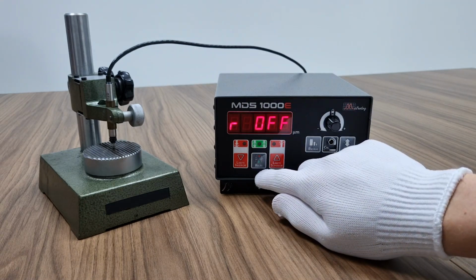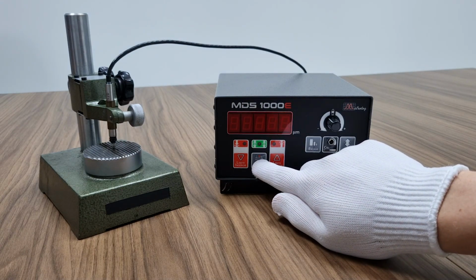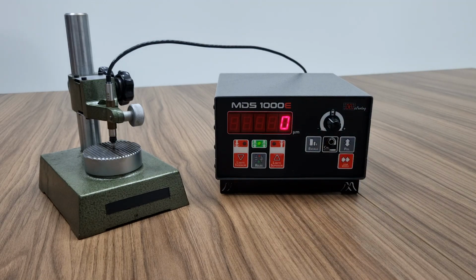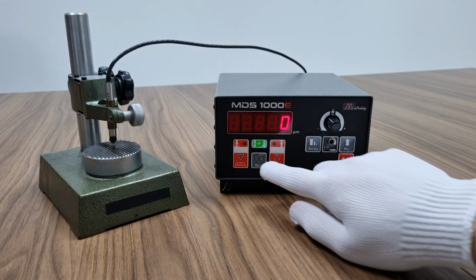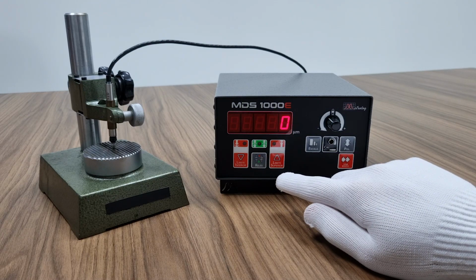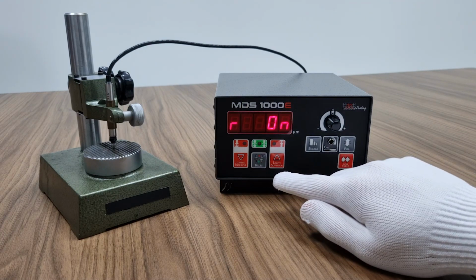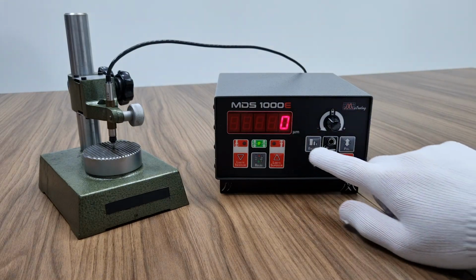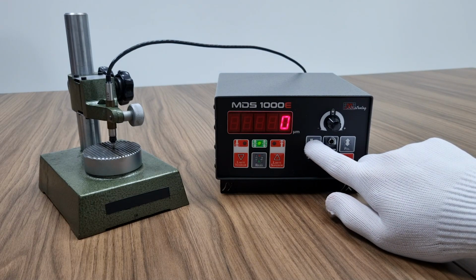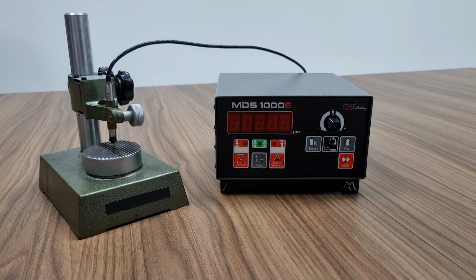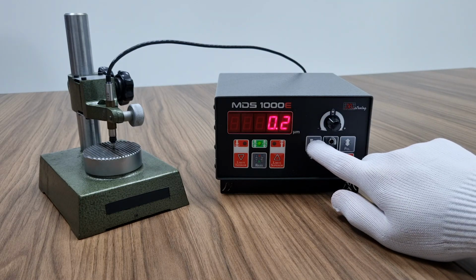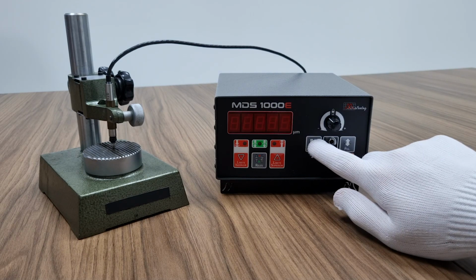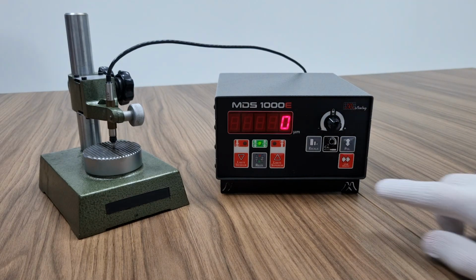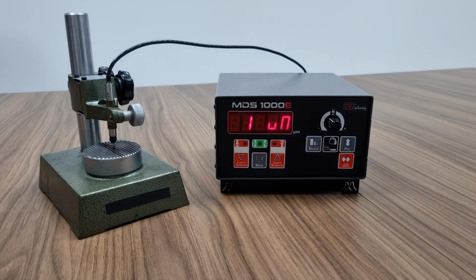The relay key allows the relay contact outputs of the tolerance limits to be activated or deactivated. To switch the operating mode, simply press the key briefly. The scale key allows you to adjust the working resolution in 1 micrometer or 0.1 micrometer. To toggle the active scale, press the key for 2 seconds. The key can be pressed briefly to query the set value.